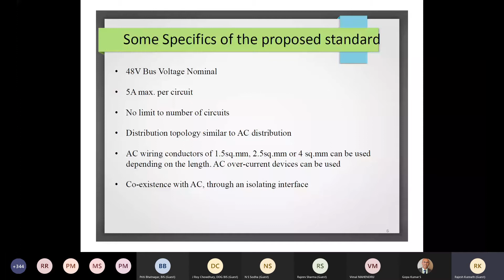So when it comes to safety, what kind of safety measures are we looking at when we look at an SELV distribution, right? The SELV, the safety extra low voltage, is essentially a floating output voltage, right? To give you an analogy of what this means, take your laptop charger, for instance, which many of you are familiar with. Depending upon the model, the voltages will vary from about 11 volts all the way up to close to 24 volts, and they have a positive and negative which has nothing to do with ground.